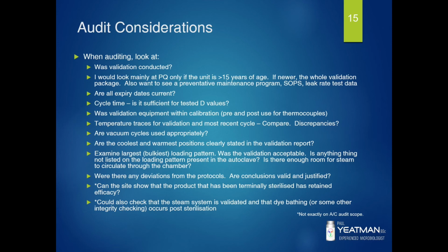So these are what I would consider the important considerations. Was validation conducted? And if it was conducted, was it prospective or retrospective? If the autoclave's new, then I'd be looking at prospective validation, which is IQ, OQ, PQ, potentially looking at URS. If it was an old autoclave, say greater than 15 years of age, IQ and OQ have probably been grandfathered, but you want to make sure that the loading patterns are current. And also you'd want to look at, say, preventive maintenance programs. The risk assessment might determine that you don't need that, but it's always a good idea to do preventive maintenance, because then the equipment's not going to keel over at a most inopportune time.